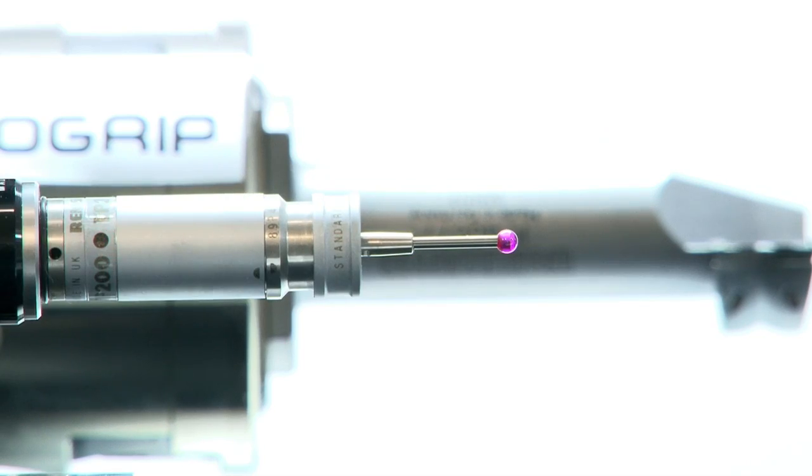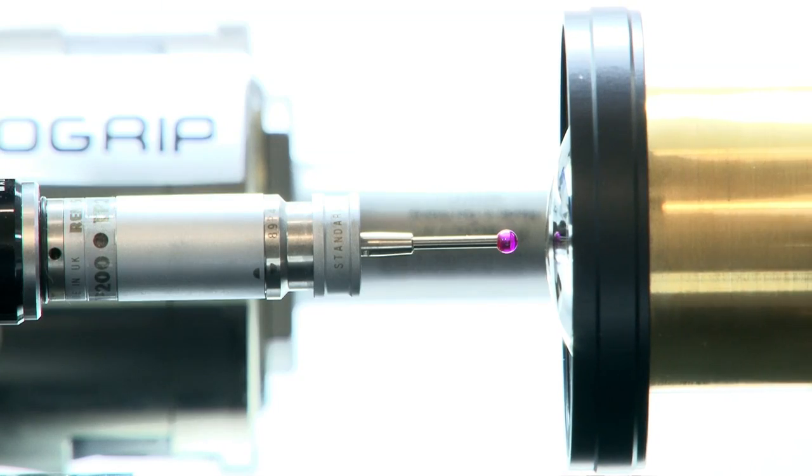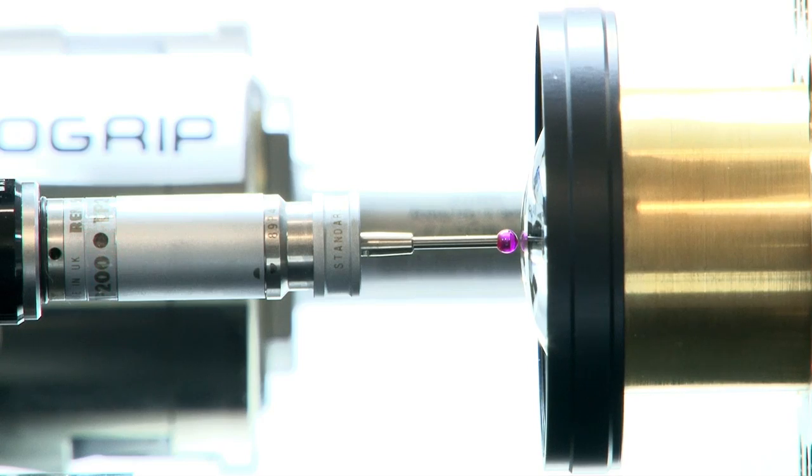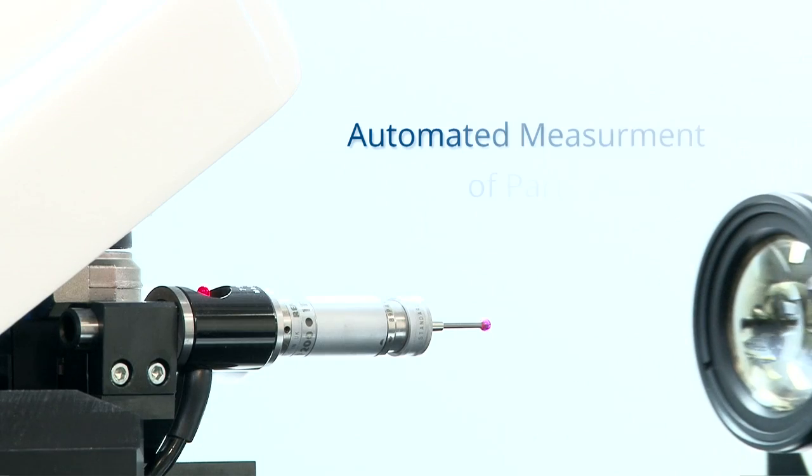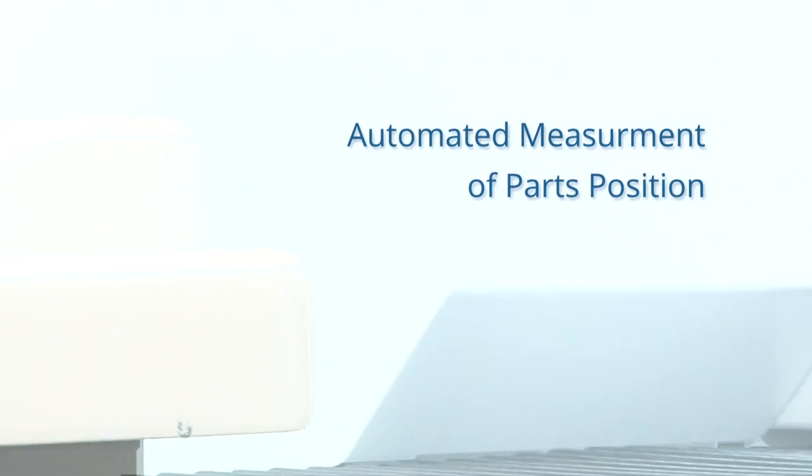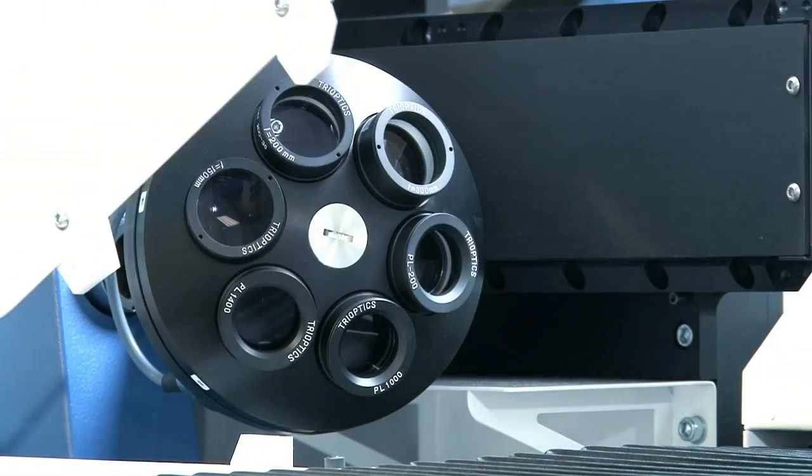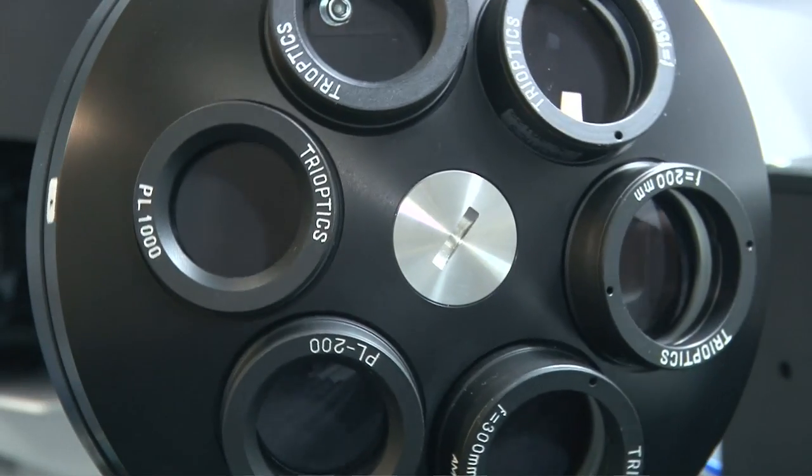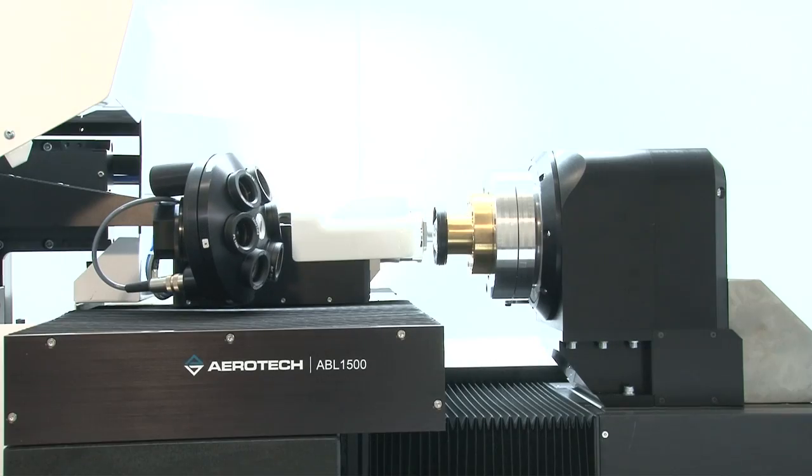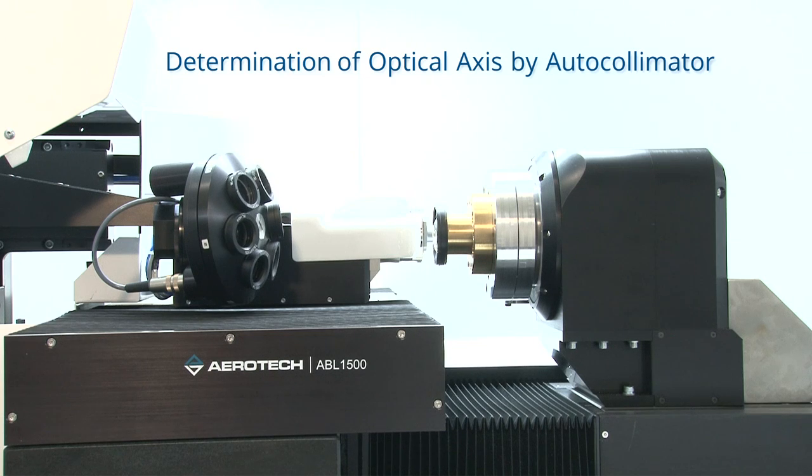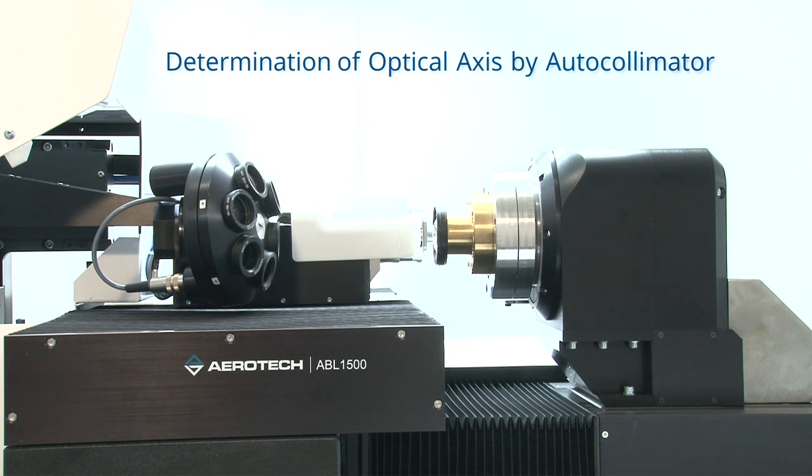Tactile or optical sensors determine the position of the lens and mount, and then transmit them to the Trioptics software. The OptiCentric software then generates the exact coordinates for determining the optical axis.